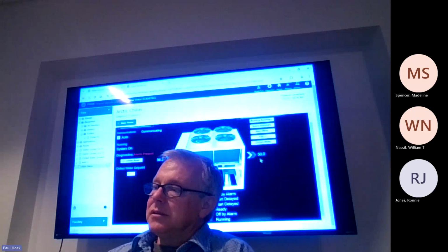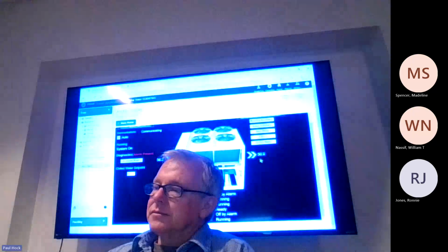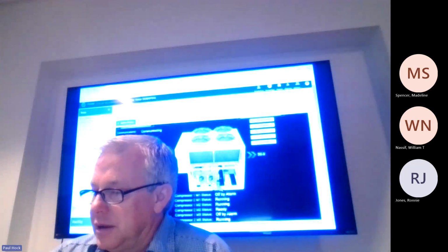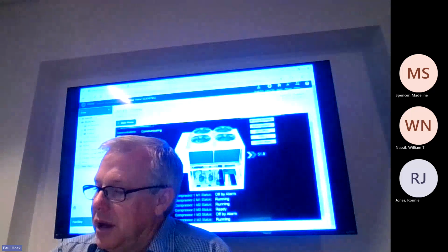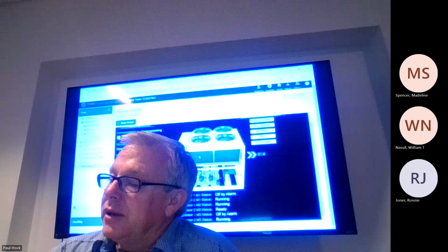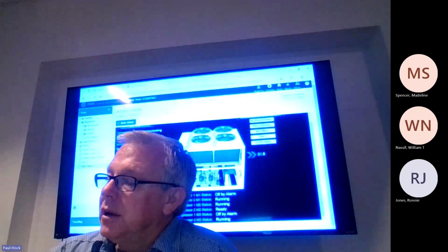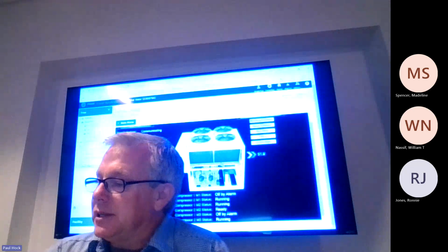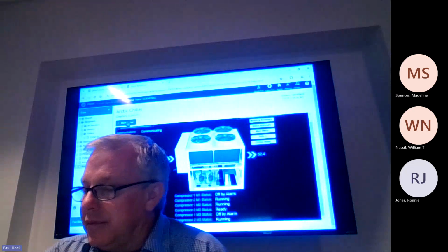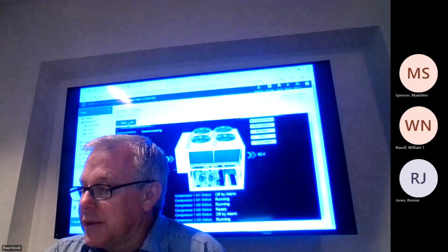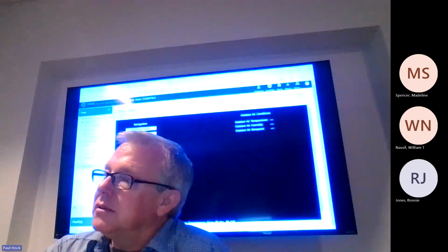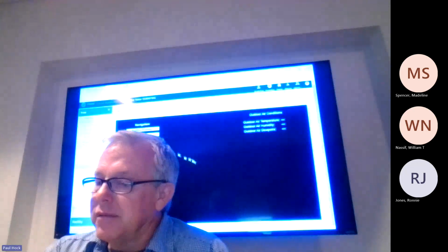What levels should those normally be at? That one's saying 58.2, the other one's saying 50.6. Are those supposed to be at specific levels? Depending on the load of the building, this one here is the return going into the chiller, so it's going to be higher. And this one should be closer to set point. Okay. It looks like it's not resetting, so I'll call Jeremy and find out the status on it.